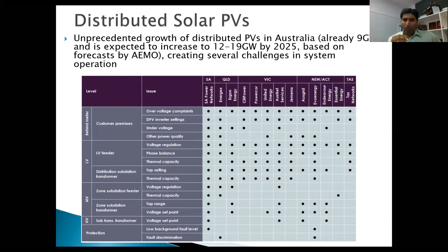Of course there is a thermal capacity problem, because sometimes the generation from all the consecutive neighborhood solar systems becomes so high that the feeder gets congested, due to the very low load in the daytime.